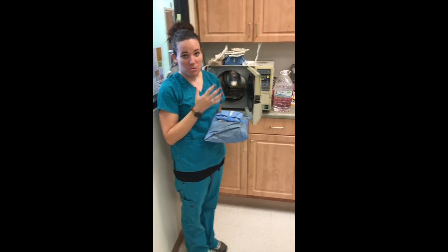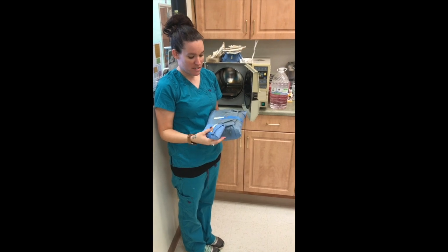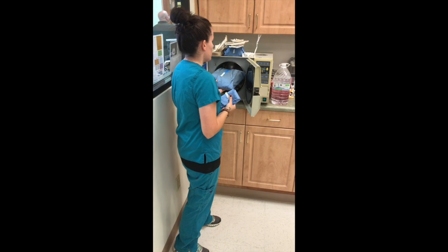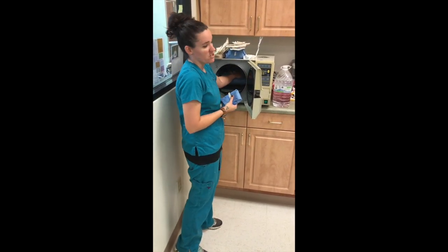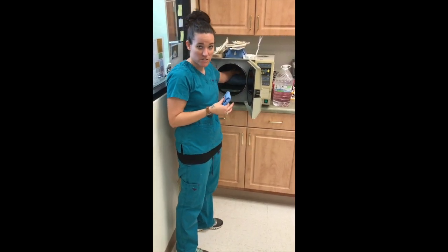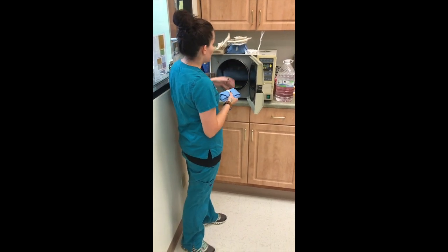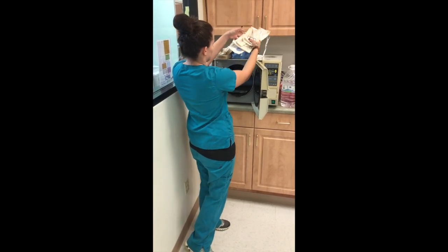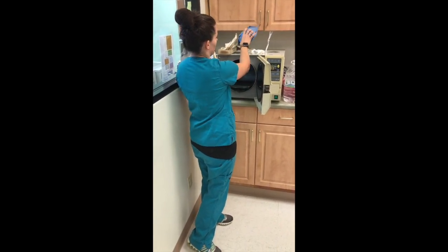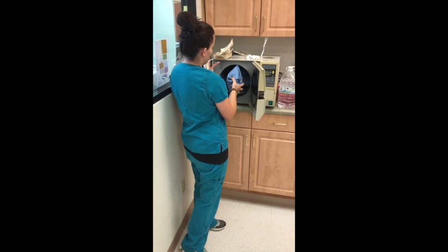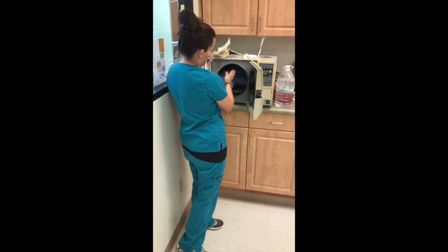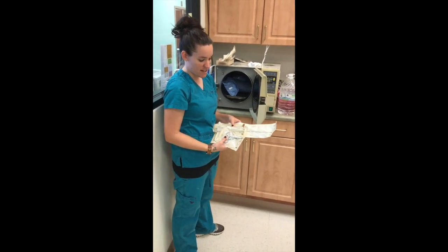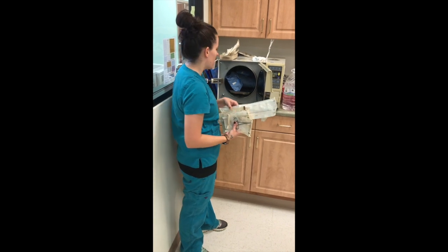Okay, so we're going to pack our autoclave with some of our packs that we've wrapped. When you're loading the autoclave, you want to not fill it too full. You want to make sure that everything can get good steam penetration so that it can be properly sterilized. So we're going to put our big stuff on the bottom here. We've got some paper things here that we're going to put in. This is a bowl that we're sterilizing. We're going to prop this up on the side a little bit to make sure it gets steam all around it. As we're putting these paper things in, we're going to pack them in nice and loose so that they can get steam through them as well.